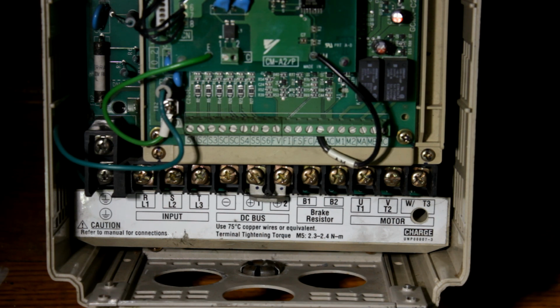Essentially all new variable frequency drives run from DC, even though they accept three-phase input anyway. What happens inside is that the three-phase input just flows through a rectifier and gets converted into DC no matter what. So yes, this one will run directly from direct current.